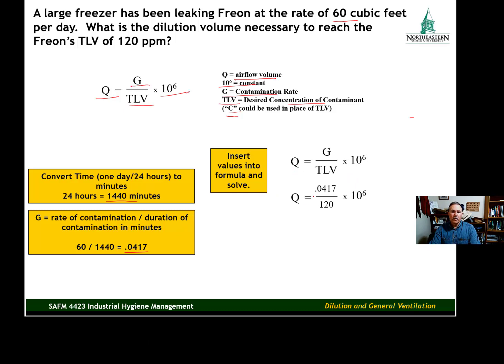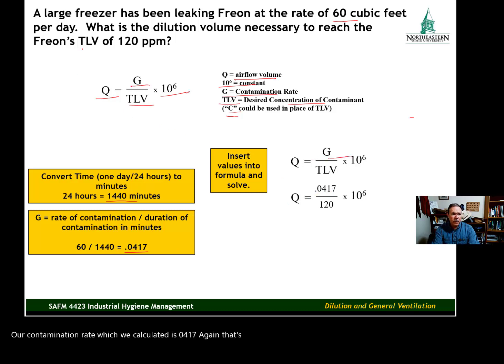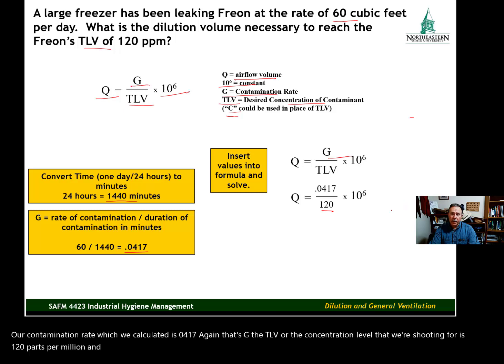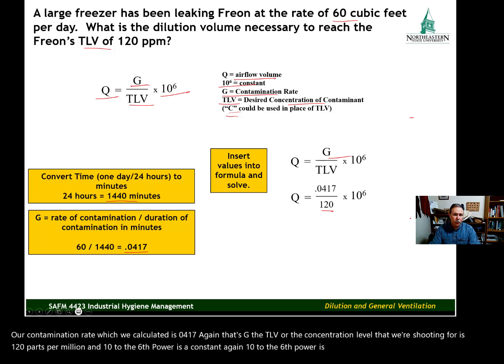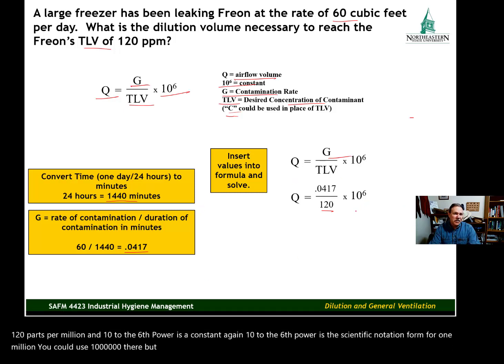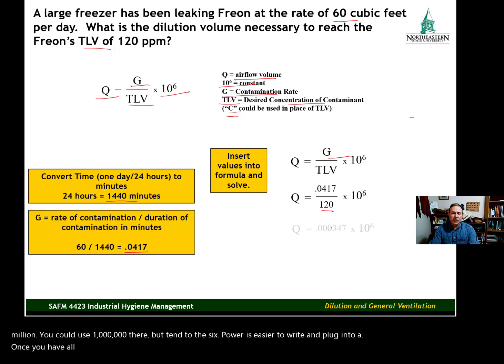Now we have everything we need to plug into the formula. Our contamination rate G is 0.0417. The TLV — the concentration level we're targeting — is 120 parts per million. And 10 to the 6th power is the constant, which is simply scientific notation for one million. Once all your numbers are plugged in, it's just division and multiplication: divide 0.0417 by 120.